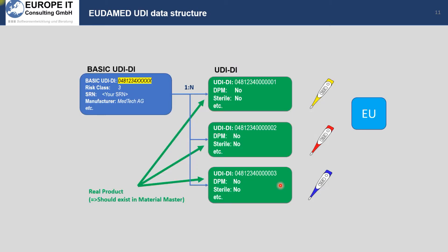The basic UDI data is built as a parent and child data structure. On the left side you have the basic UDIDI, which is like a product family, and on the right side you have your UDIDIs — these are your individual products in your system. For example, a thermometer can exist in different variants like yellow, red, and blue, and you assign each variant to the basic UDIDI product family.